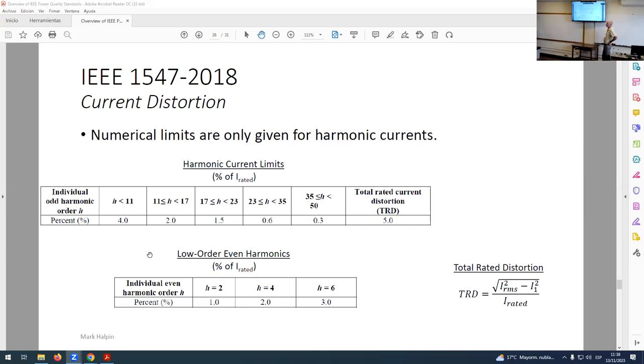The next version of IEEE 519 will have something like this. Okay? All right, it's called total rated distortion. Well, obviously all of these things are percentages, but percentage of what? They're always taken as a percentage of the rated generating equipment capability. Limits are not assessed based on a percentage of output at a particular point. They're always assessed based on a percentage of the rated capability. So that's the reason we call it total rated distortion, because in the denominator, of course, is the rated current.